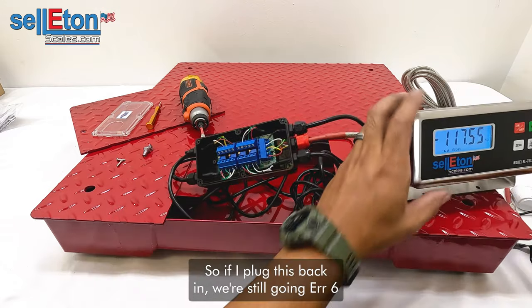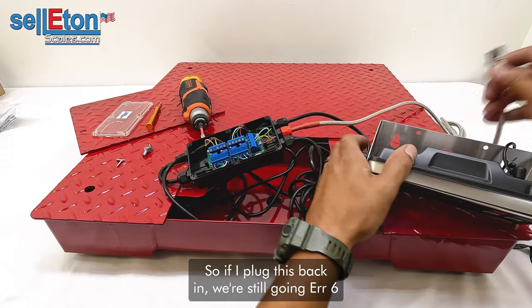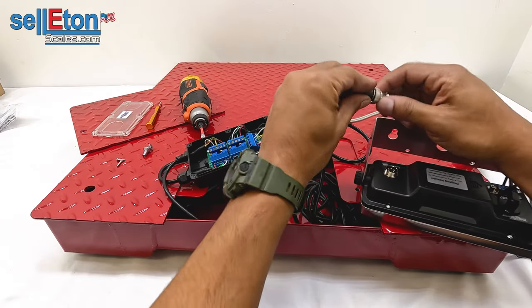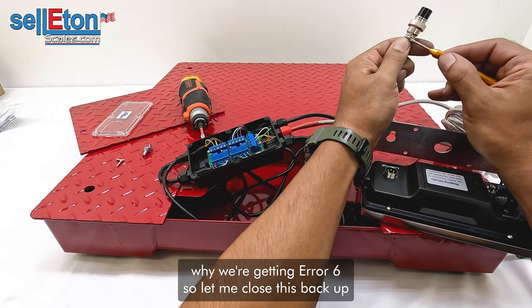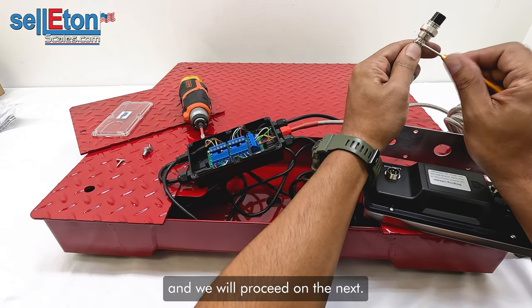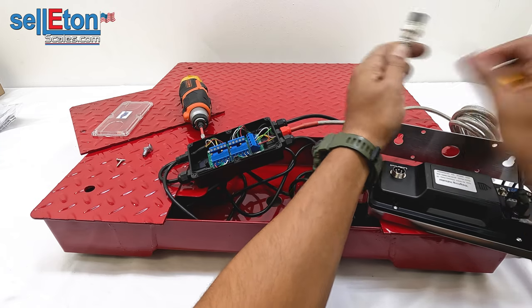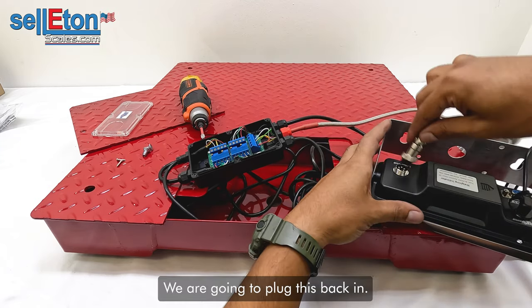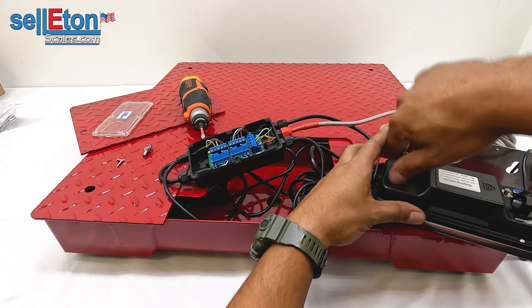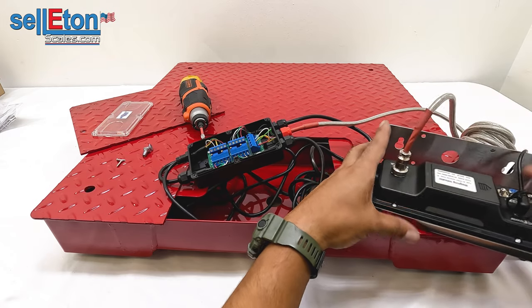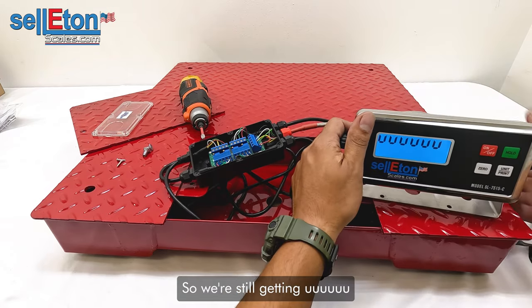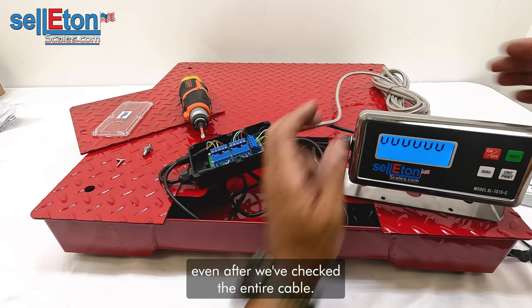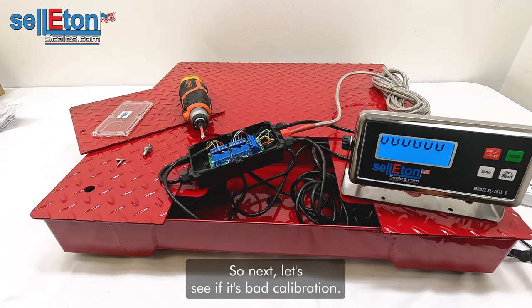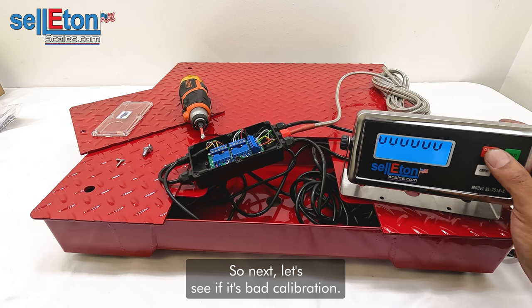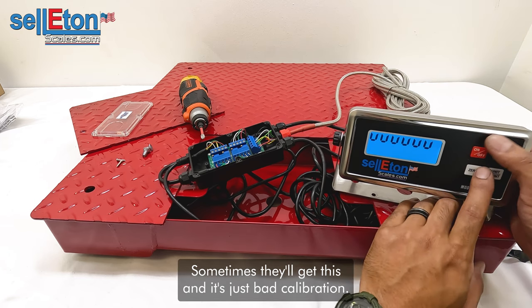If I plug this back in and we're still getting error 6, we're going to go over another way to identify why we're getting error 6. Let me close this back up and we will proceed to the next. I'm going to plug this back in. Great. So we're still getting USE even after we've checked the entire cable. Next, let's see if it's a bad calibration. Sometimes you'll get this and it's just a bad calibration.